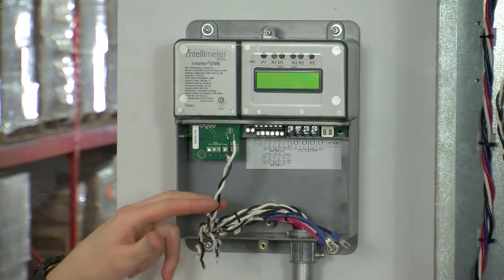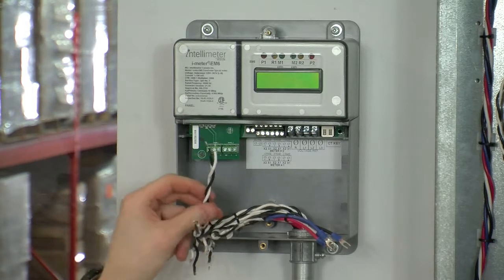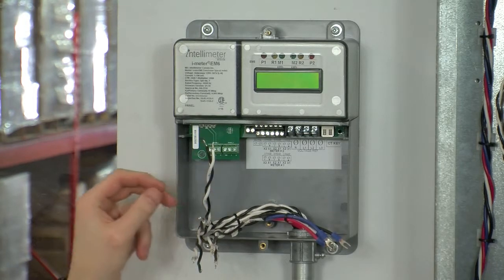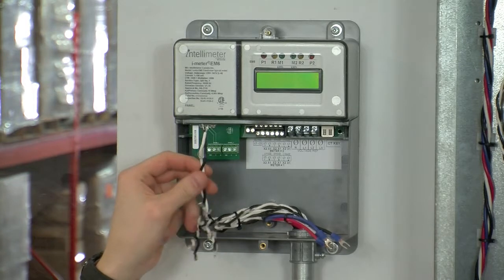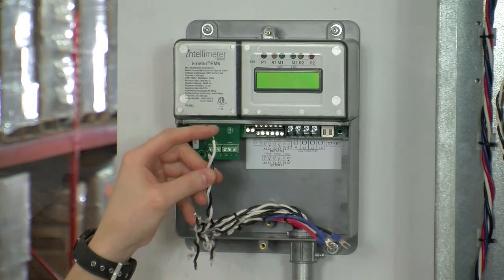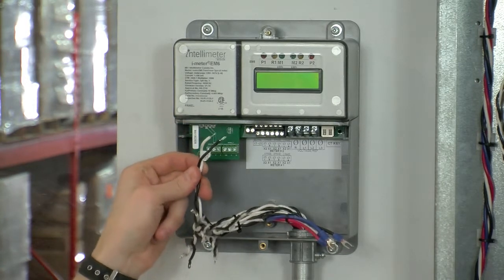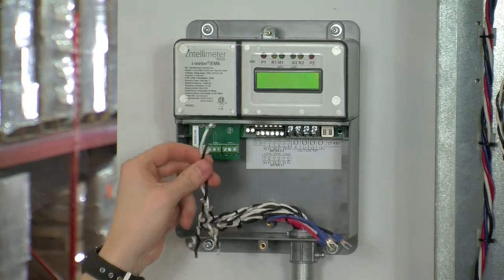So we're going to use a precision screwdriver to terminate the CT leads into their corresponding terminals. Starting with CT1, we use black for negative and white for positive. We want to double check the labels on the CT leads to ensure that each CT is being terminated in its correct slot.